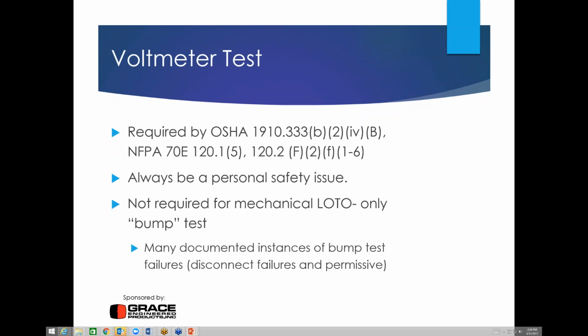So as we move forward, Don had mentioned the voltmeter test, or the voltage test instrument that will be used. And this is required by OSHA under 1910.333 and under NFPA 70E 120.15, which is your voltage test instrument. From the time that we hit apprentice school to the time we end our careers as journeymen, the voltmeter has always been our personal safety device or personal safety tool, because we use it on a regular basis to verify that there is no energy there.